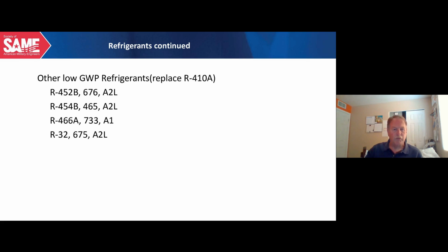They're all A2L refrigerants. And A2L refrigerants, just as a refresher, are basically what we call mildly flammable refrigerants, and they have a relatively slow burn velocity. That's why they're separated from the rest of the A2 refrigerants. What I would like to point out is one of these low GWP refrigerants is R466A. Has a global warming potential of 733 and has an A1 safety classification, which will then separate it from the A2Ls in the places that it can be used and the charge limits that you will see from that.